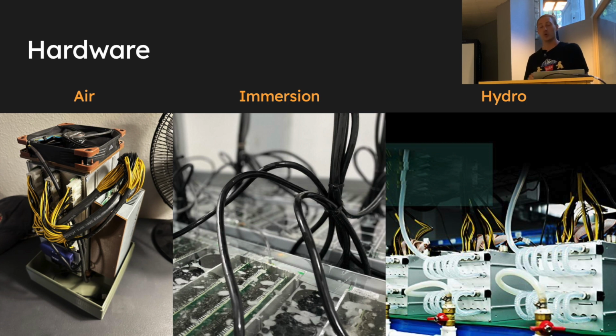And here you don't have to cool all the other components. You also don't have to deal with the dielectric fluid, which can be expensive. It can be toxic in some manners. It's heavier. So there are conflicting opinions. Some people don't like immersion, some people do. There are trade-offs to each. In terms of heat transfer, both of them, the fluids are much better at transferring this energy over distances. That's because they have that high specific heat capacity, which means it takes more energy to change the temperature of it, right?